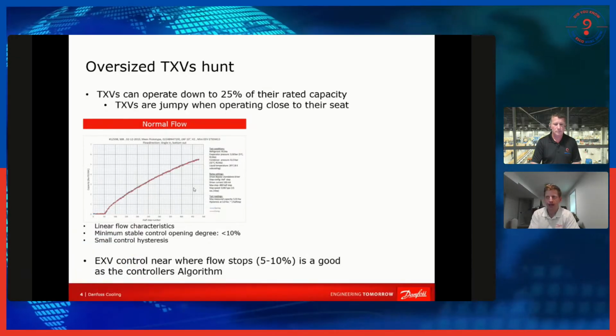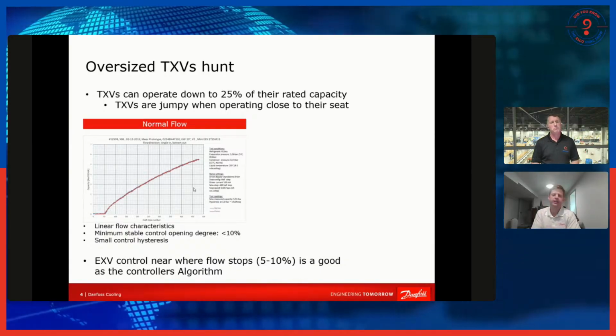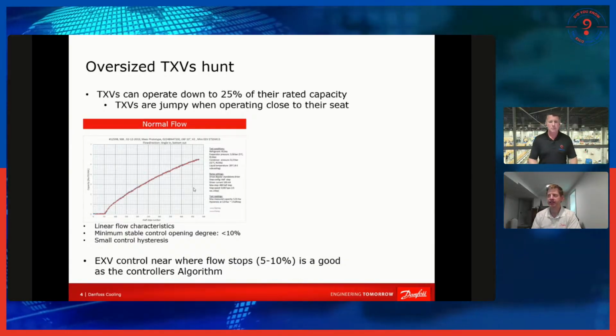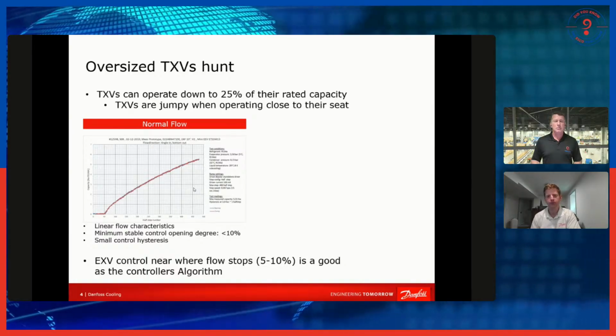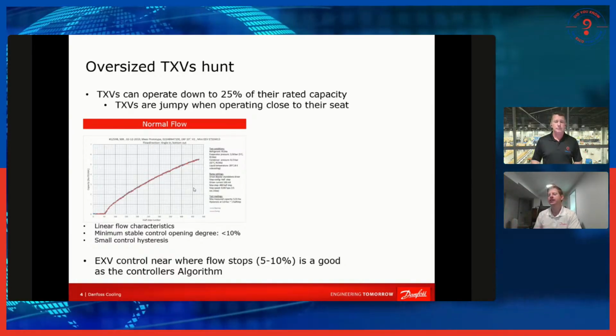So one of the things to start with is oversized TXVs tend to hunt. And for a balance ported TXV, they can still operate pretty effectively down to 25% of their rated capacity. But once you get them down near that point, they get pretty jumpy.